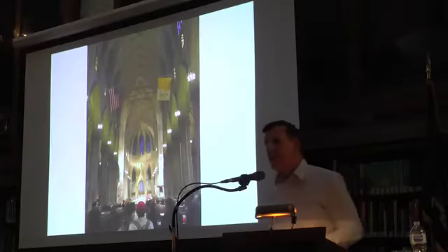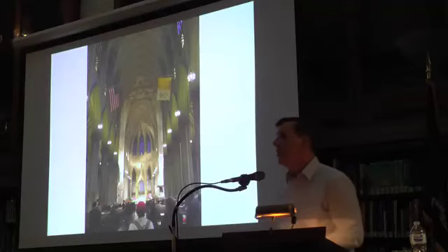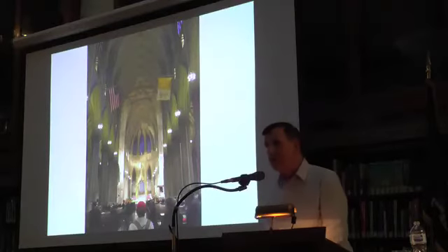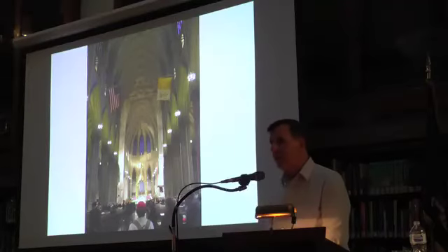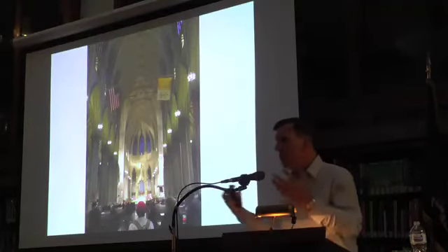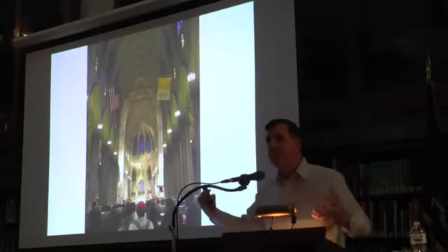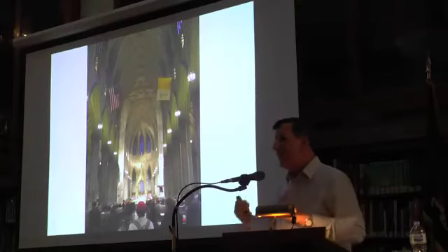If you were in a cathedral like this, or even a space like we're in right here, and you did a heat loss on the building because you're going to replace the boiler, you will find that the number you come up with is so dramatically greater than the actual boiler size and radiation size that has been in that building for 100 years. So how can you possibly heat that building with something so small? And everything in your being, if you're a heating professional, is telling you to put in something bigger because you don't want to make a mistake.